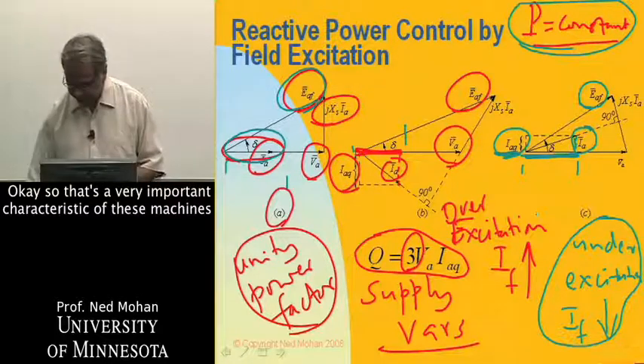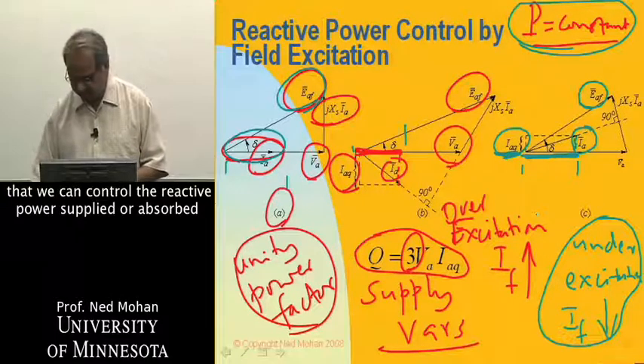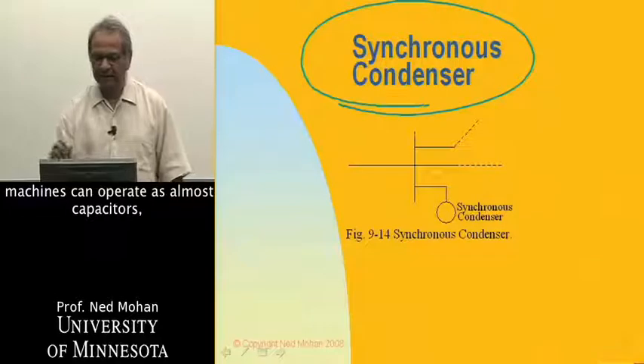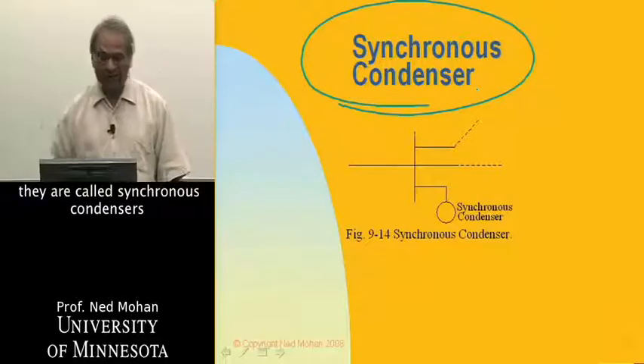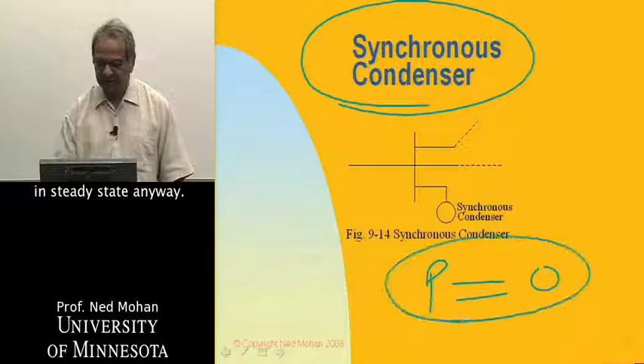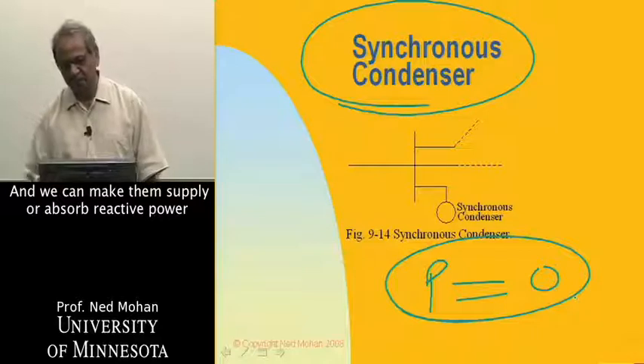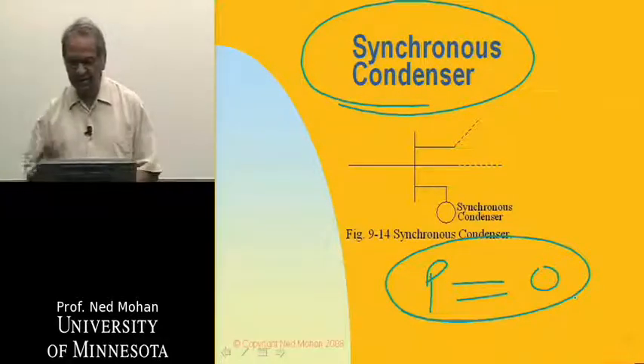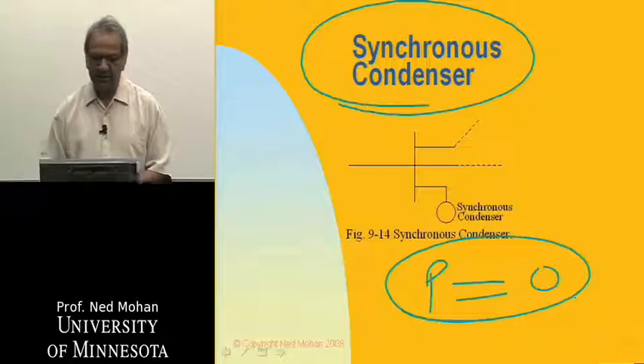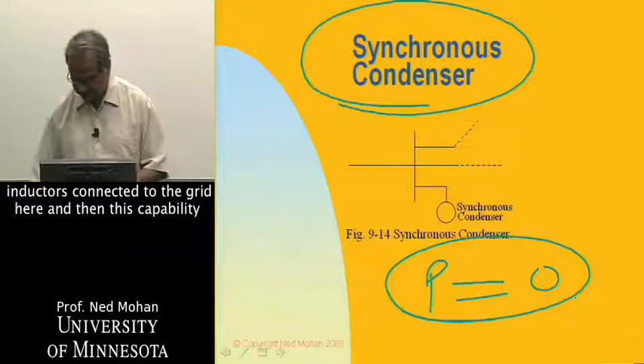That's a very important characteristic of these machines — we can control the reactive power supplied or absorbed. Quite often these synchronous machines can operate as almost capacitors, called synchronous condensers, where real power transfer is essentially zero in steady state. Because of the inertia of these machines they are able to supply some real power under dynamic conditions, giving better characteristics than simply connecting capacitors or inductors to the grid.